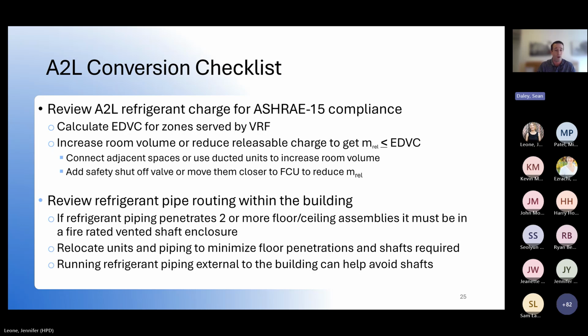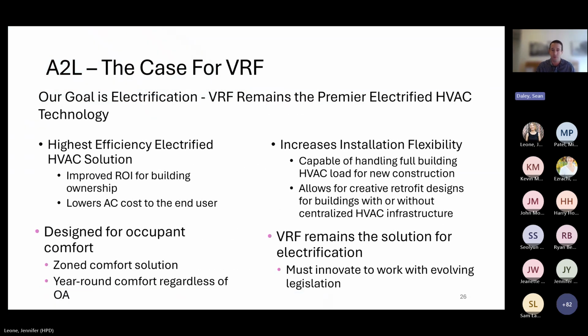That could mean running refrigerant piping externally, or redesigning the layout of the systems so that your piping is serving a single floor or 2 floors and not going beyond that. We're going to have to get creative on how we lay the systems out and route the piping to try to avoid some of these more restrictive requirements, like the fire-rated vented shafts. So that's all I have for the A2L design considerations.